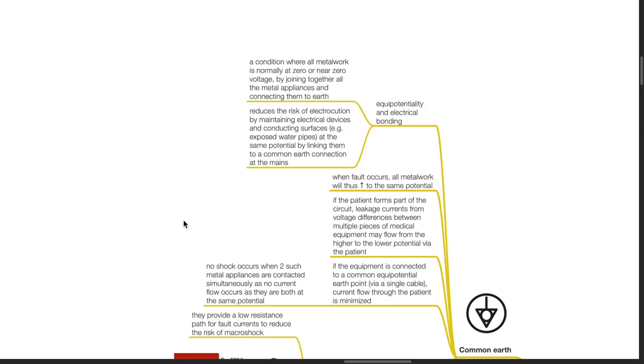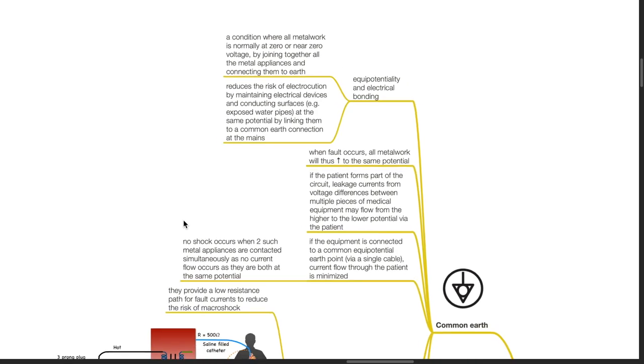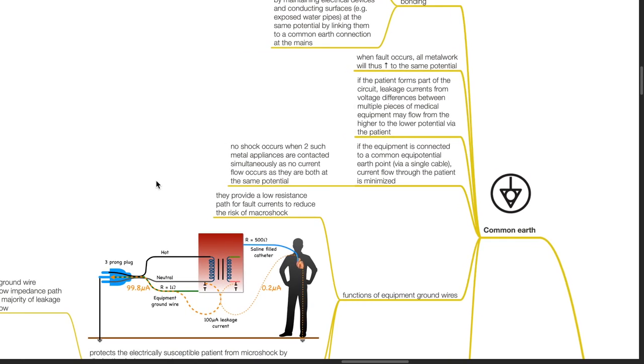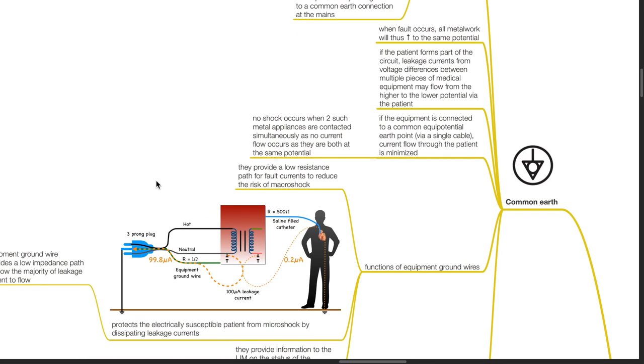Common earth. Equipotentiality and electrical bonding is a condition where all metalwork is normally at zero or near zero voltage by joining together all metal appliances and connecting them to earth. This reduces the risk of electrocution by maintaining electrical devices and conducting surfaces such as exposed water pipes at the same potential by linking them to a common earth connection at the mains. When fault occurs, all metalwork will increase to the same potential. If the patient forms part of the circuit, leakage currents from voltage differences between multiple pieces of medical equipment may flow via the patient. If the equipment is connected to a common equipotential earth point via a single cable, current flow through the patient is minimized. No shock occurs when two such metal appliances are contacted simultaneously as no current flow occurs since they are at the same potential.